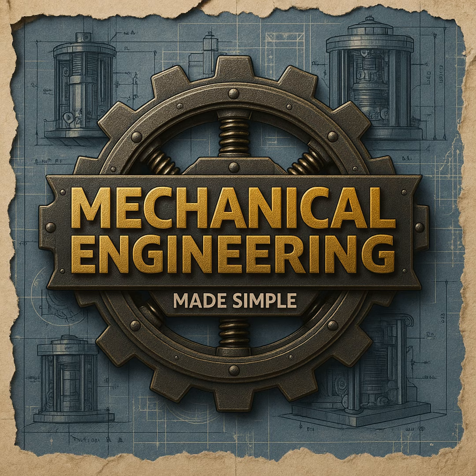Electrohydrodynamic enhancement, EHD. Yes. The text outlines using a high-voltage, low-current electric field to literally blast the condensate film off the surface of the tube. I mean, it sounds like complete science fiction, but the physics are highly effective. You have to keep in mind it only works on fluids that have very low electrical conductivity. Oh. If you tried this with regular water, it would immediately short out. But it works beautifully with refrigerants.